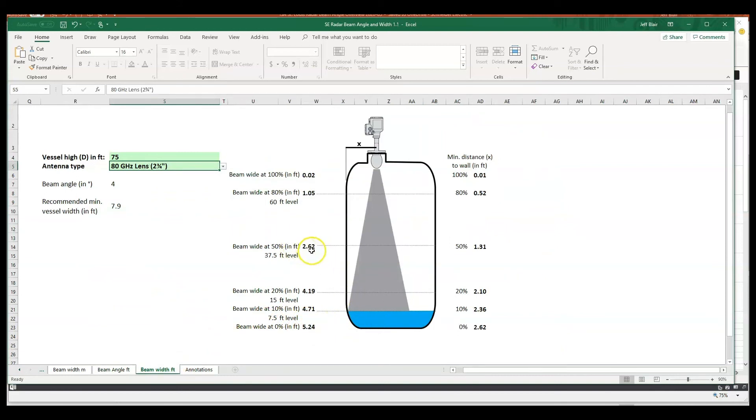At 50% high, it's going to be 2.62 feet. At 80% high, it's going to be just a little over a foot. So you can actually use these radar beam angle calculators to figure out how big the beam is going to be - is it going to intersect a thermal well, a baffle, a heating coil, some other obstacle or internal obstacle that may be in the tank? And you can envision how big the beam is going to be and where it's going to go.